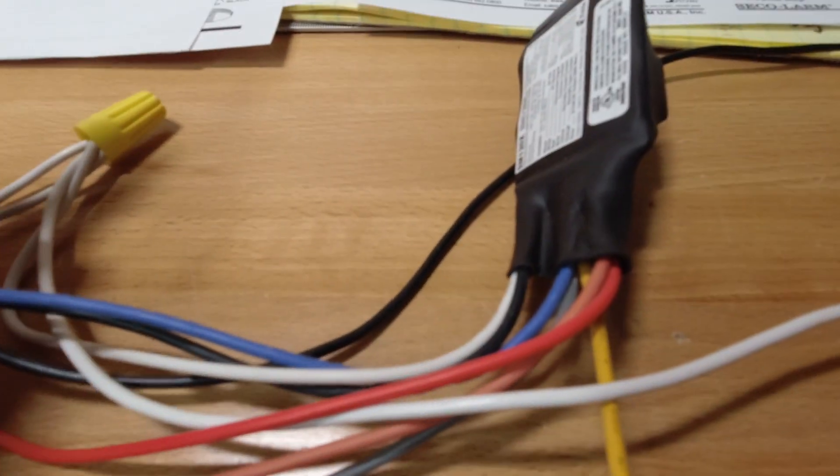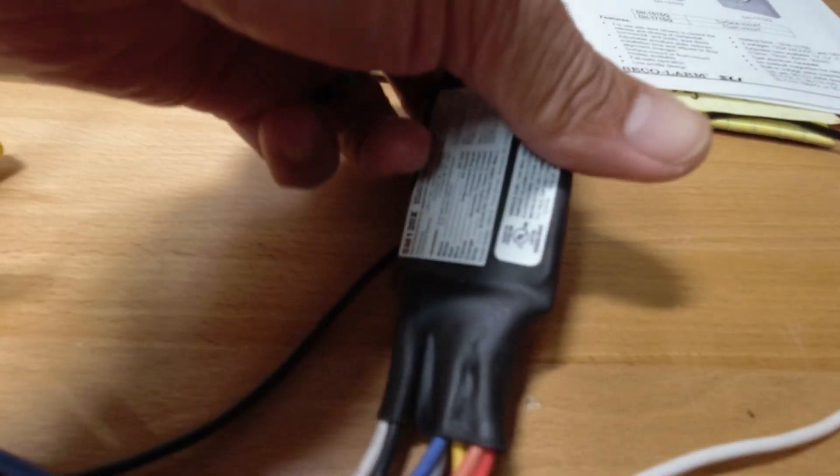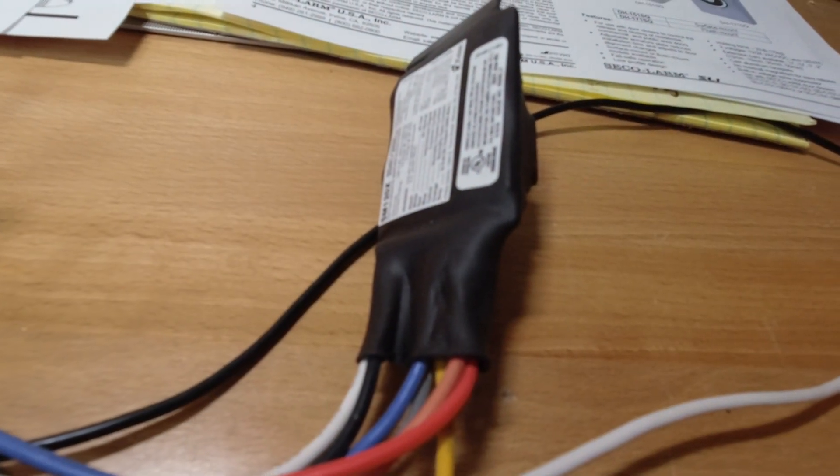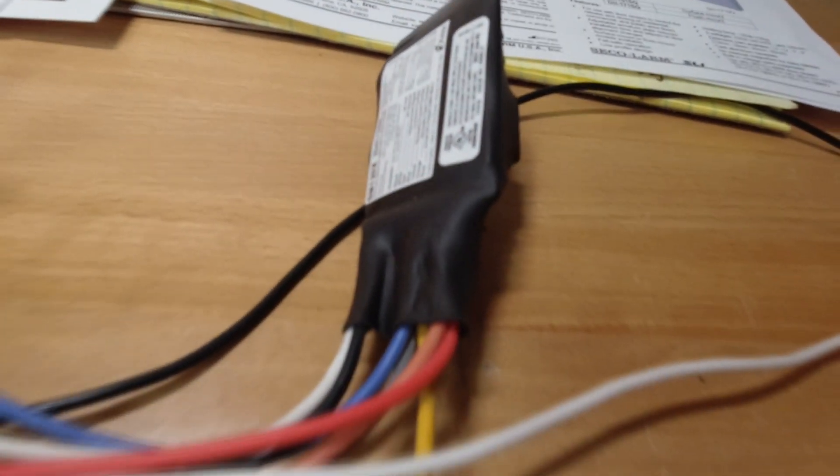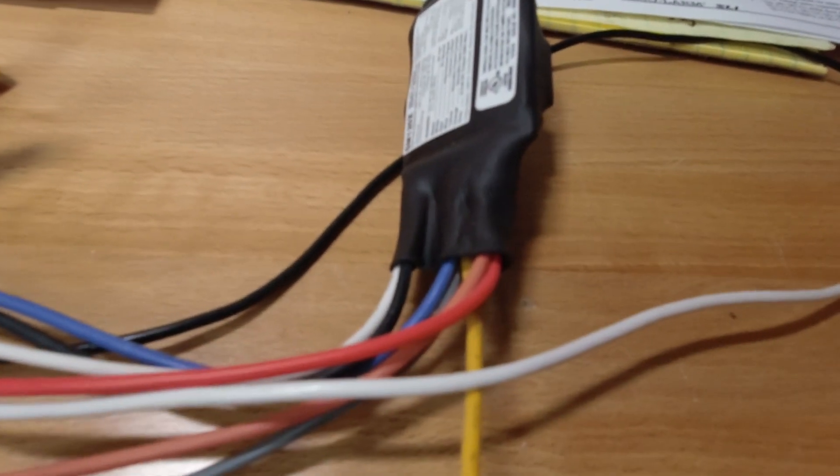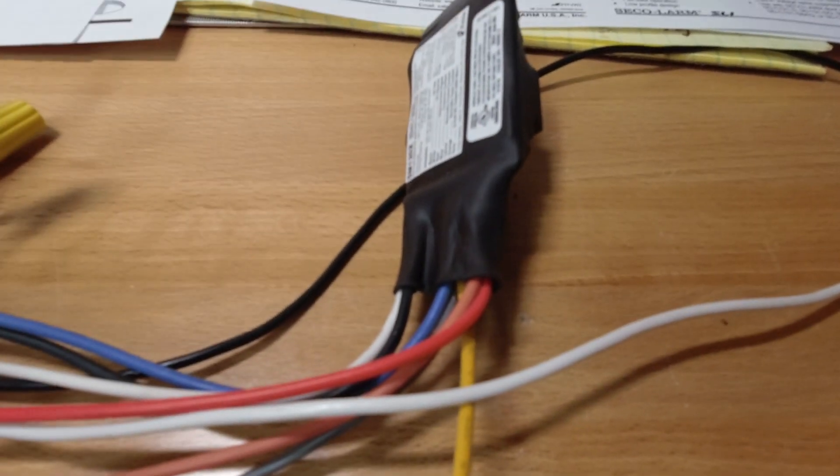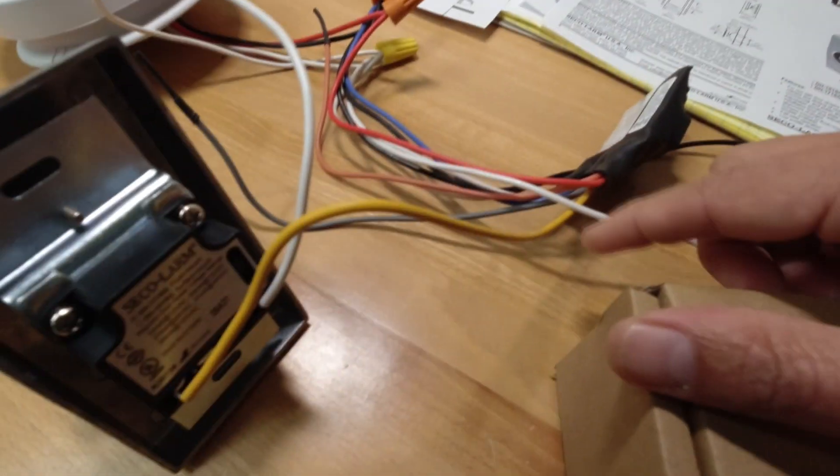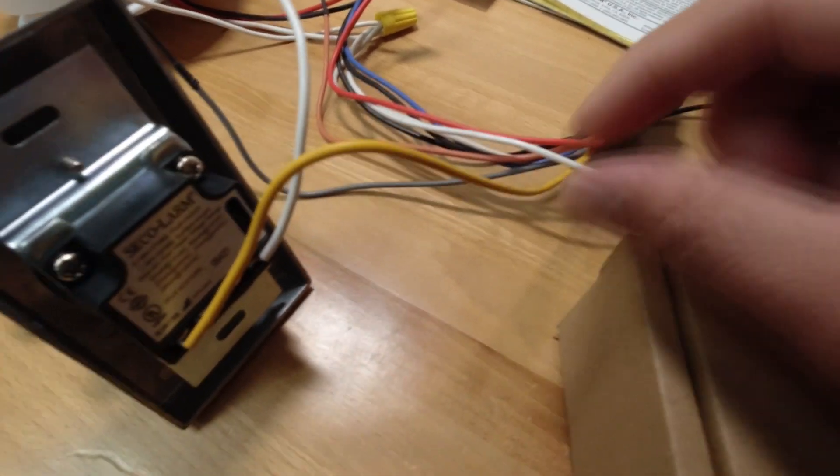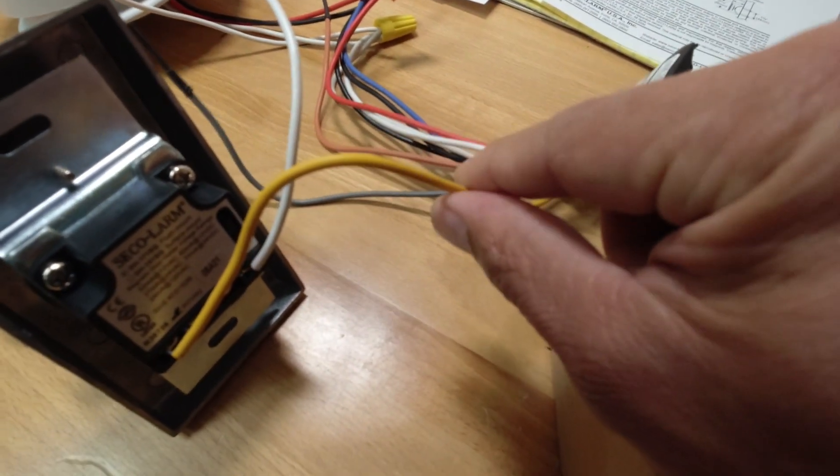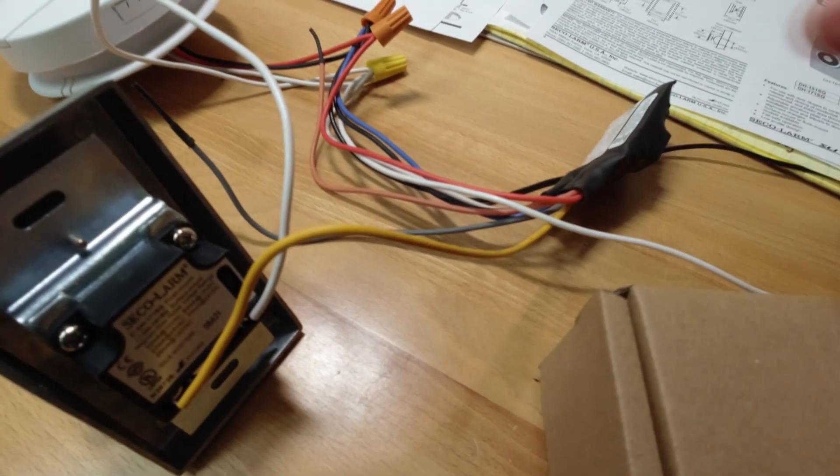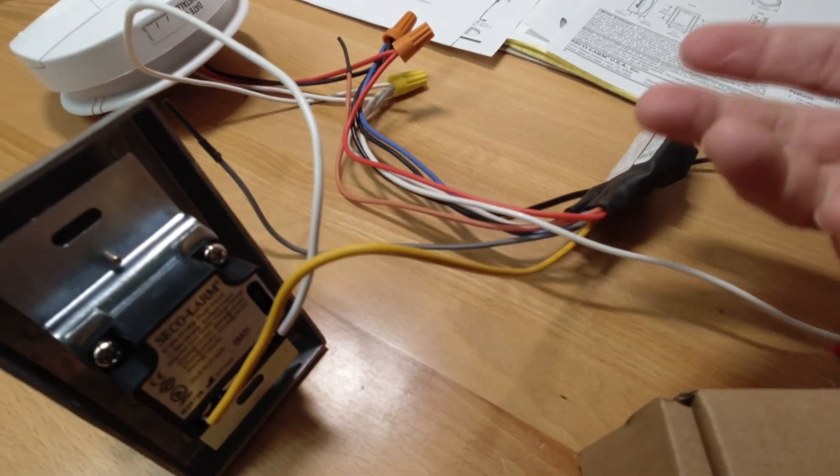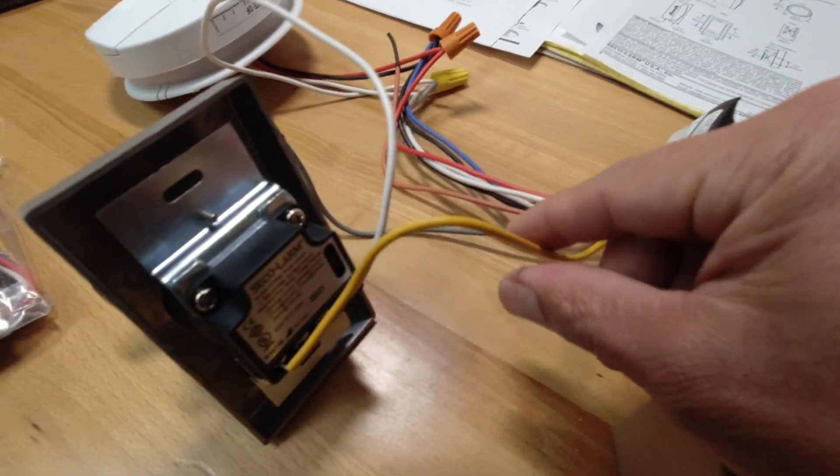And that 124 volts, 120 volts, is going to get used for the normally open relay or normally closed relay. So I'm currently using as a normally closed relay. And so when it triggers, it will disable this 120 volts because it's normally closed. It will open it when it triggers, okay?